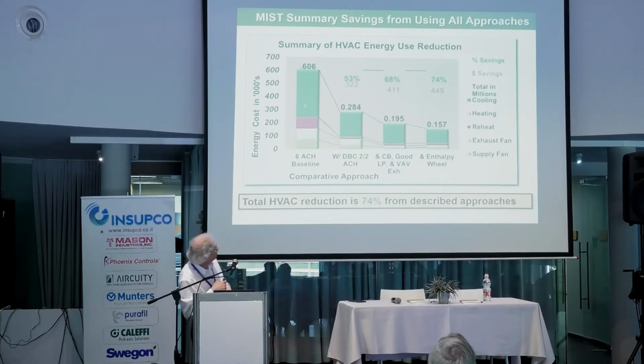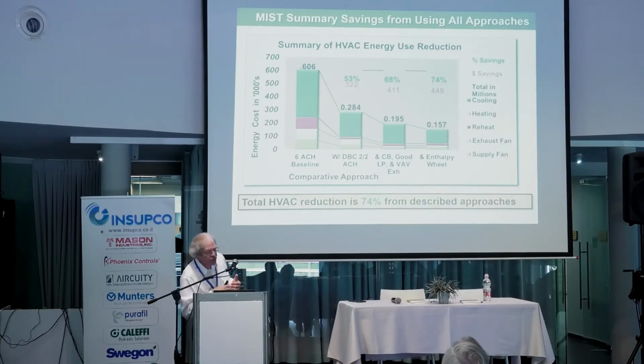This would have been more of a standard design running at 6 air changes with more conventional technology. Using demand-based control running at 2 air changes day and night, with the ability to purge up to about 14 air changes when needed, that reduced the airflow and reduced the energy by about 53%.